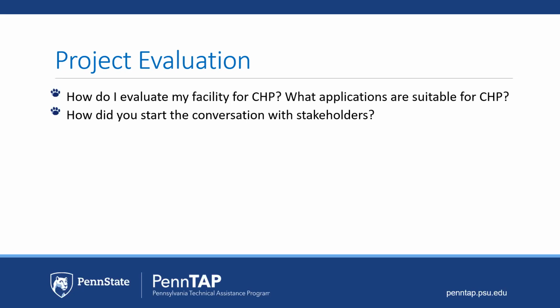The conversation always starts at, what are we really looking for? Energy efficiency or reliability? For Allegheny Health Network, we were building a brand new hospital up north of Pittsburgh in Wexford, and we started evaluating the most energy efficient options. We compared the status quo, traditional chiller and boiler plant, versus a CHP, and we find it interesting because a hospital has a dire need for continuous utilities 24/7. So CHP was a no-brainer.